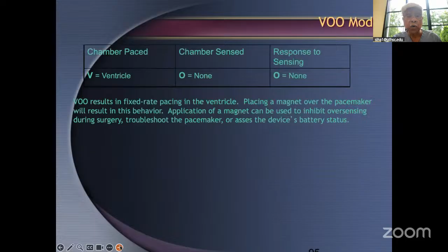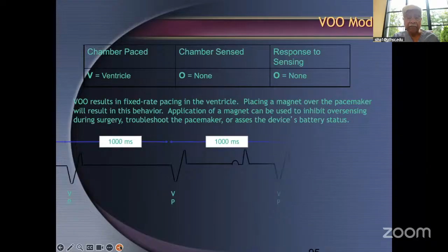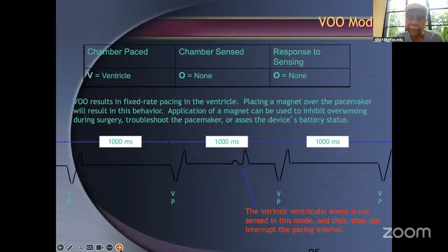If you make it VOO, that means it results in fixed rate pacing in the ventricle. Put the magnet over the pacemaker, it will result in this behavior. The application of a magnet can be used to inhibit oversensing during surgery, troubleshoot the pacemaker, or assess the device's battery status. So what happens here? V-paced, V-paced, V-paced. This beat came, it did not inhibit the pacemaker. This is VOO pacing.